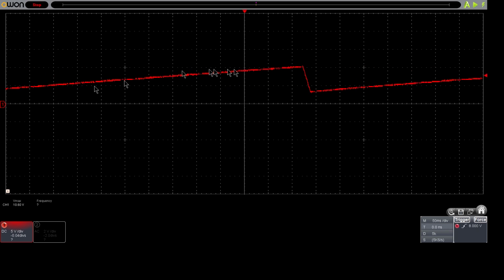You can see it was ramping up and discharging, ramping up and discharging, but now we've frozen it. You can see it ramping up as that capacitor charges, getting to the point where the switch mode power supply tries to kick in, and it does, but the bootstrap supply doesn't come and take over, so the voltage on the capacitor ramps down again to a point where it can no longer be used and the unit shuts down.